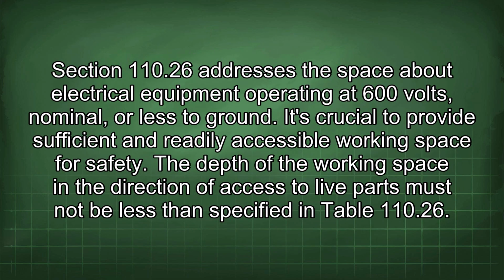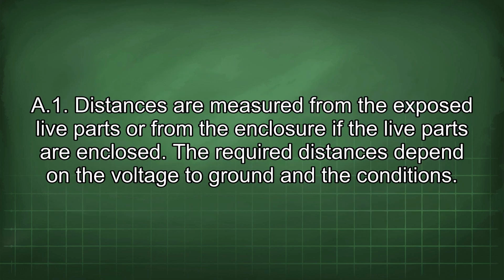Section 110.26 addresses the space about electrical equipment operating at 600 volts, nominal or less to ground. It's crucial to provide sufficient and readily accessible working space for safety. The depth of the working space and the direction of access to live parts must not be less than specified in Table 110.26(A)(1). Distances are measured from the exposed live parts or from the enclosure if the live parts are enclosed. The required distances depend on the voltage to ground and the condition.